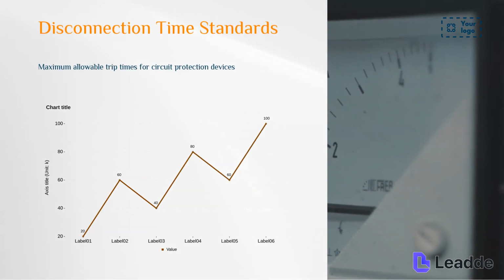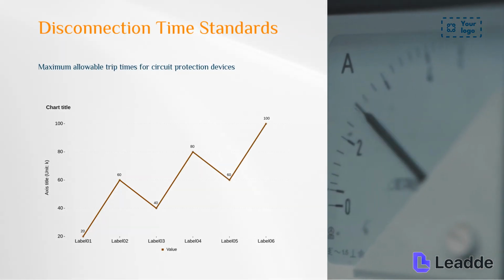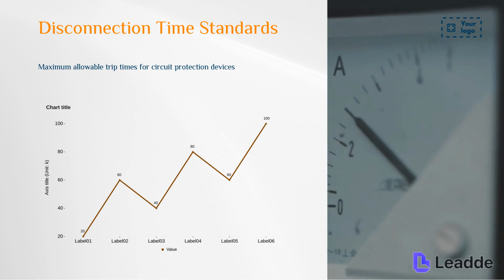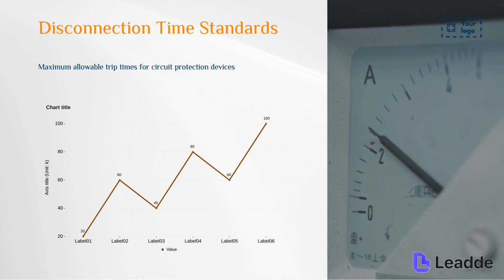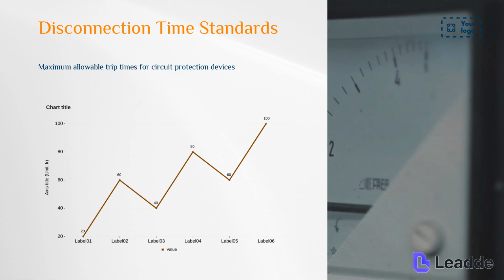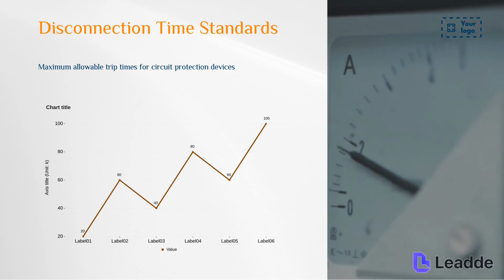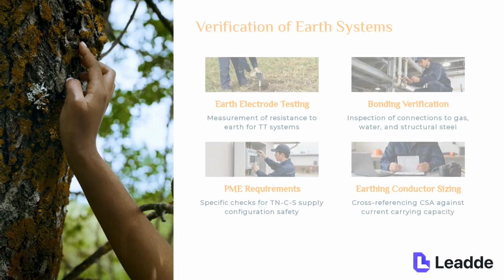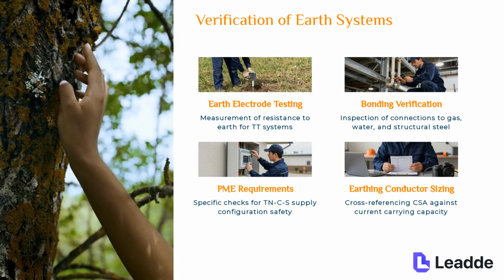This section is dedicated to disconnection time standards. We will review the maximum allowable trip times for various circuit protection devices to ensure they operate within the required safety parameters. Next, we will cover the verification of earth systems.